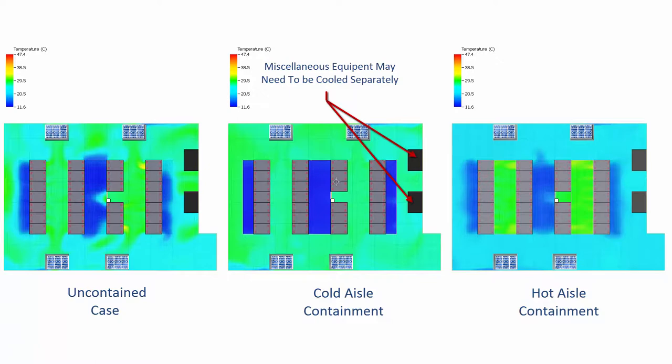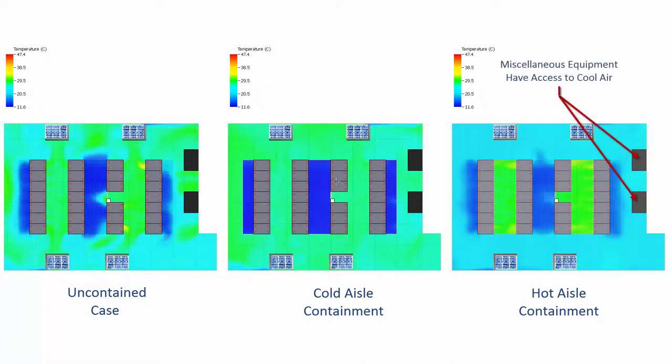Unlike the cold aisle containment configuration, the hot aisle system does not require any special consideration for non-rack mounted equipment. As well as reducing the mixing of supply and exhaust air, hot aisle containment configuration also increases efficiency by providing a net increase in the ACU return temperature. Increased return temperatures enable better heat exchange across the cooling coils and therefore increase the efficiency of the cooling units.